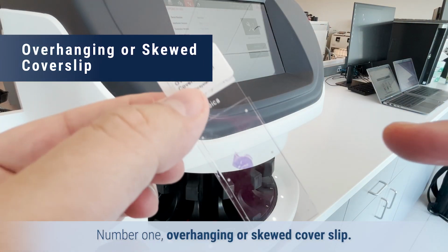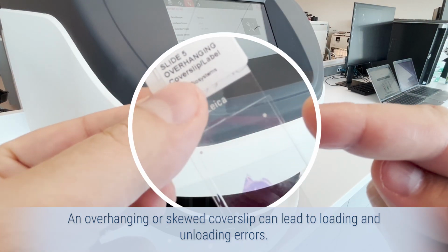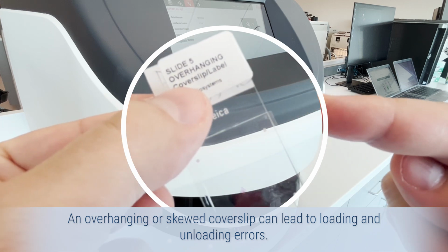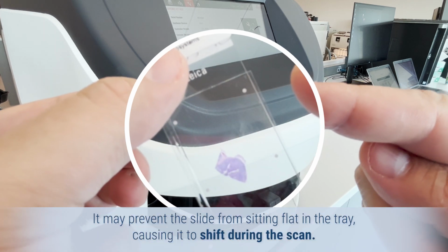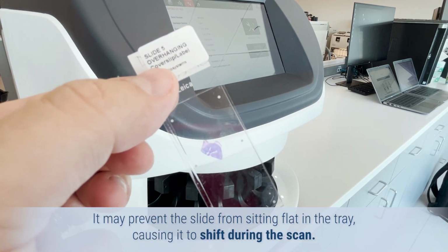Number 1, overhanging or skewed cover slip. An overhanging or skewed cover slip can lead to loading and unloading errors. It may prevent the slide from sitting flat in the tray, causing it to shift during the scan.